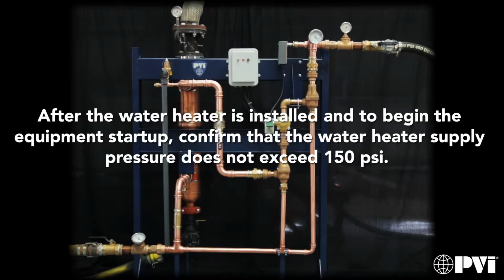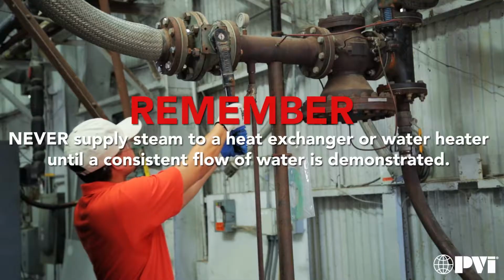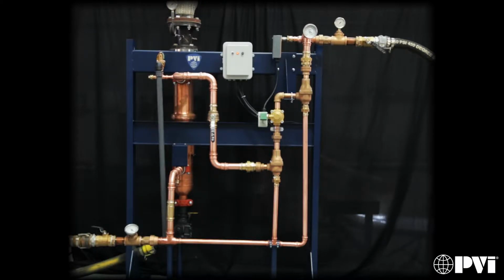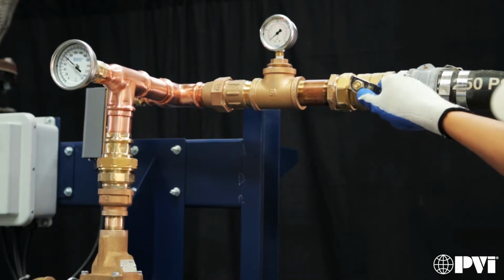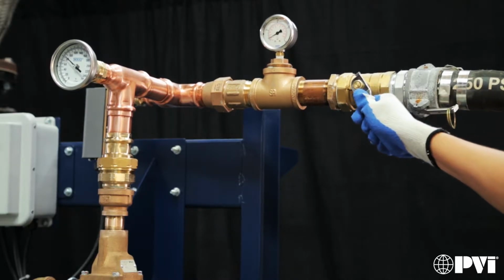Startup. After the water heater is installed, and to begin the equipment startup, confirm that the water heater supply pressure does not exceed 150 psi. Remember, never supply steam to a heat exchanger or water heater until a consistent flow of water is demonstrated. Confirm the main steam stop valve upstream of the water heater is closed. Confirm hot water outlet valve is closed.